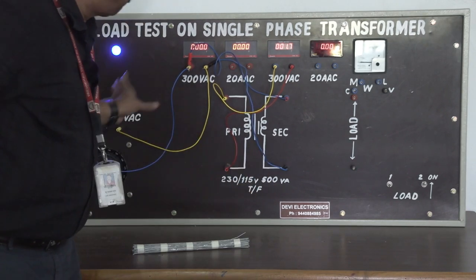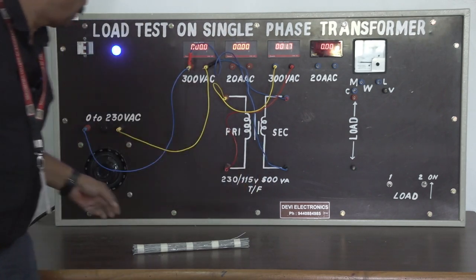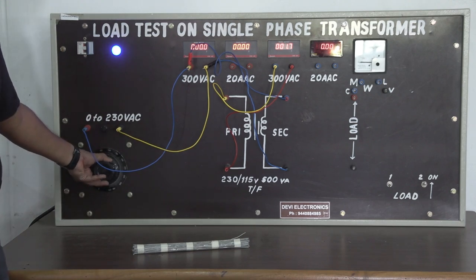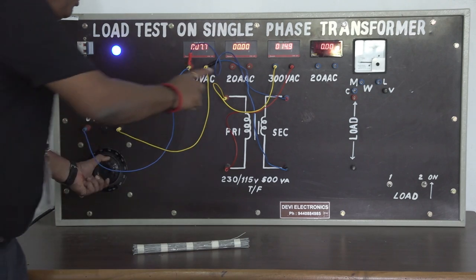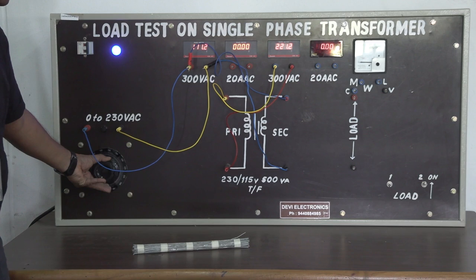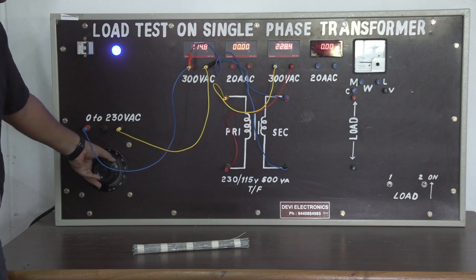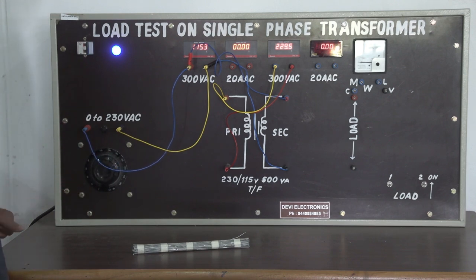Remember, we should not exceed 115 on this side, since the input voltage is going to the secondary side. So carefully I will apply 115 volts. You have to observe this voltmeter, carefully adjusting the input voltage to 115, making sure it does not exceed that, because that is the rated voltage.